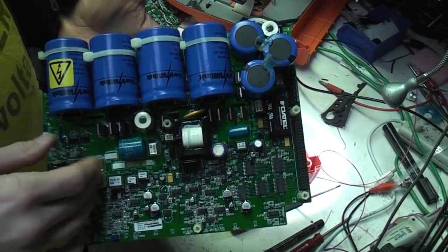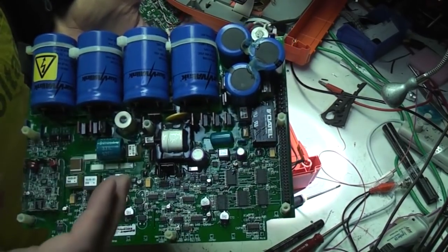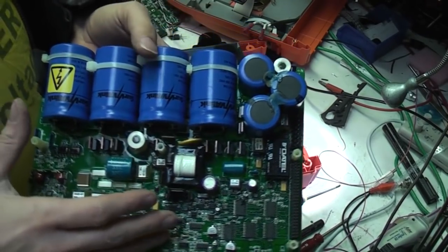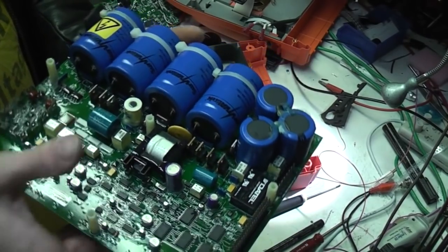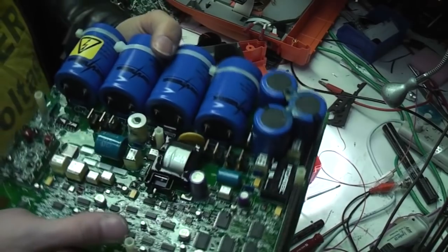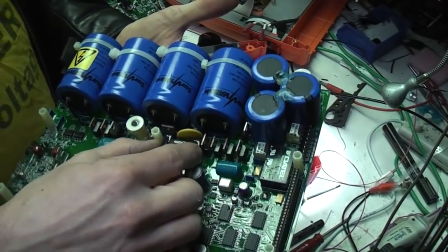Looking through some of the information, I'm just wondering if these capacitors are actually a completely separate system because it mentions high and low energy pulses. So it may well be that depending on its analysis of the heart it can decide whether to give a higher or lower energy defibrillation.